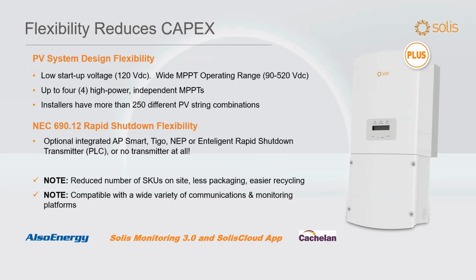And of course it goes all the way up to 520 in the operating range, so you get this wide operating range that lets you pull power in the early morning and late evening. These inverters, even with 10% loading, are still over 97% efficient. It blows me away, truthfully. What's happened in PV string inverter technologies is we're seeing better surge capabilities, better handling of these wide operating ranges, and the toughness of these products has proven itself through the years.